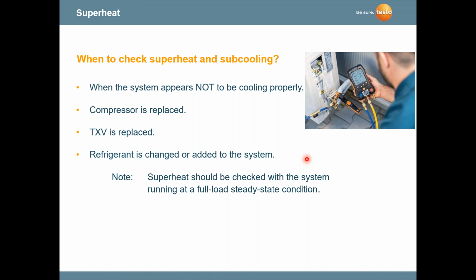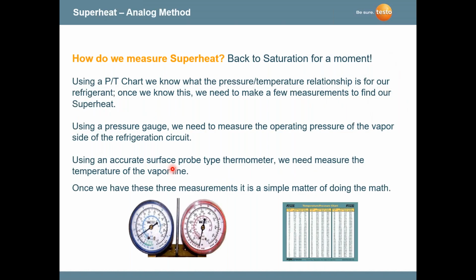When we're checking superheat and subcooling, why do we check it? Well, we need to check it when the system is not cooling properly, any time we break into the system, or if the compressor is replaced, the TXV is replaced, the refrigerant charge is changed, or refrigerant was added to the system. Superheat and subcooling need to be checked in an AC system.